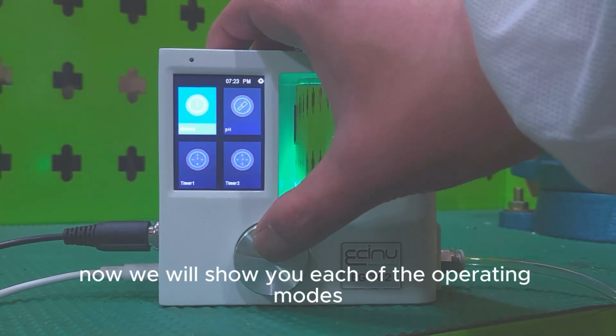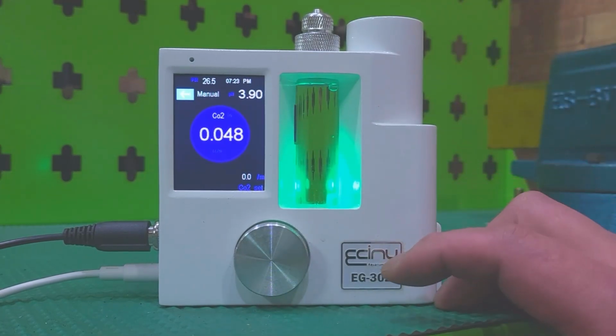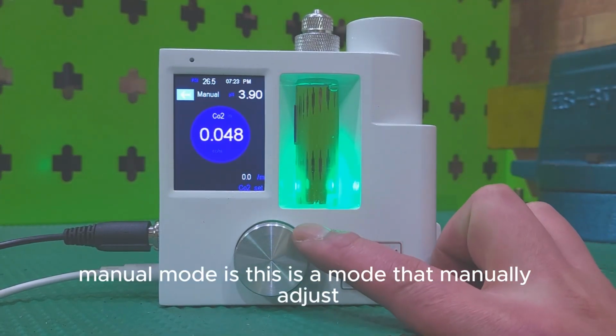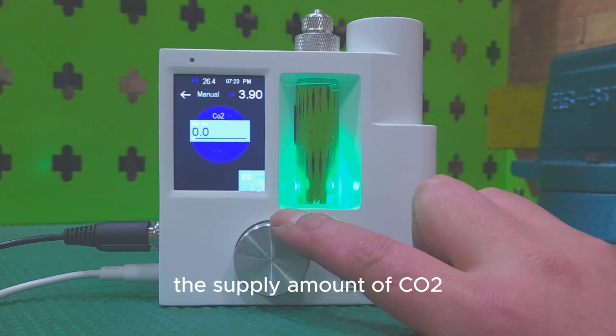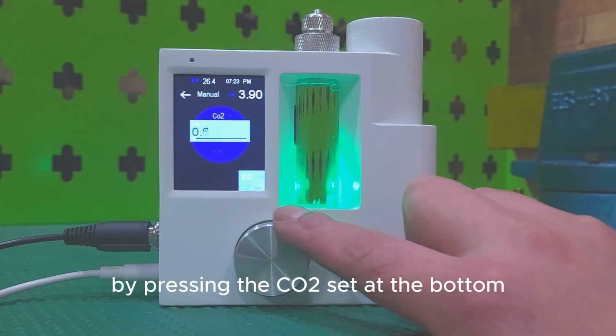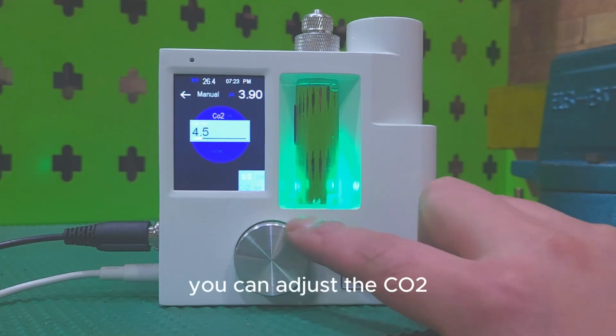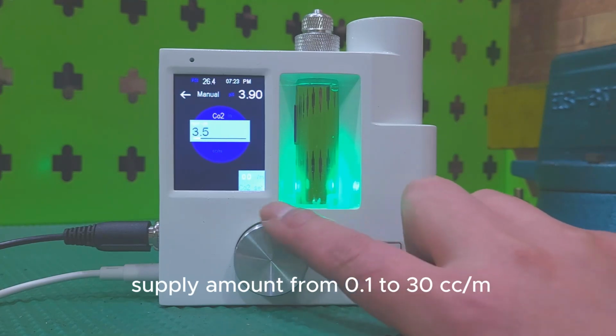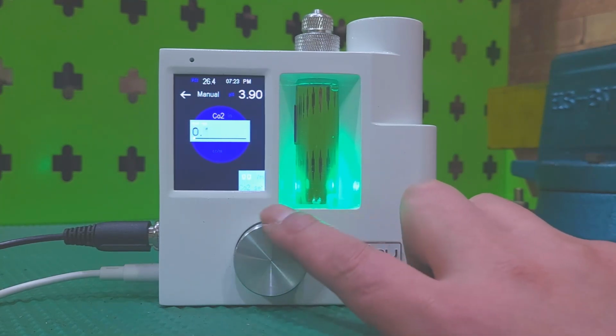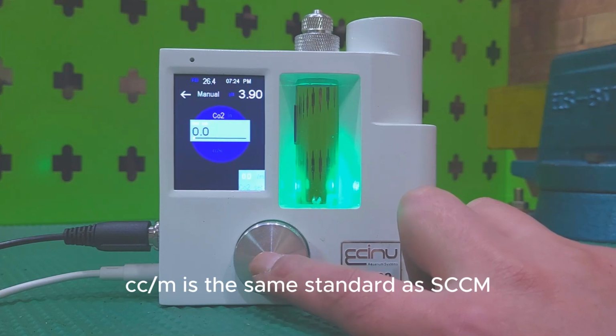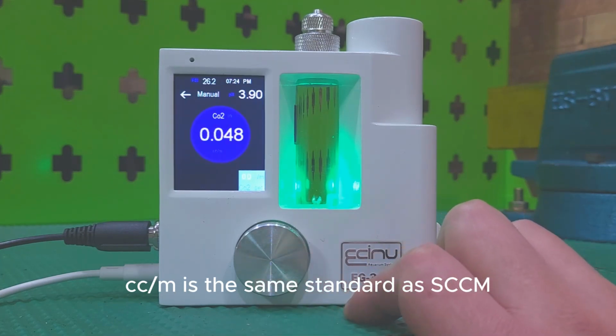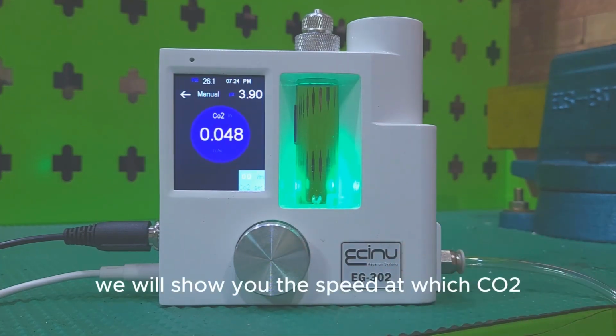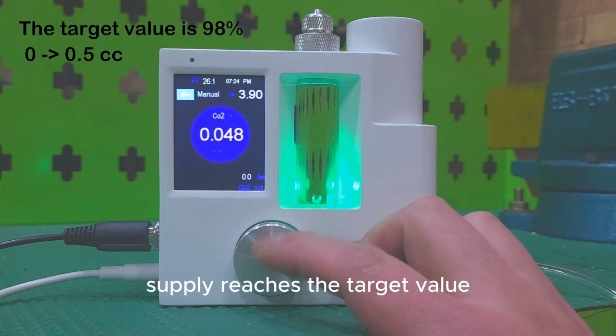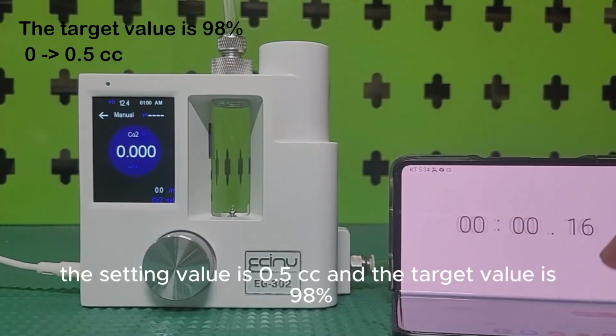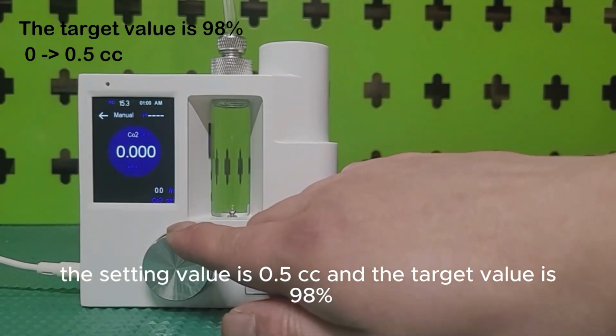Now we will show you each of the operating modes. Manual mode is a mode that manually adjusts the supply amount of CO2. By pressing the CO2 set at the bottom, you can adjust the CO2 supply amount from 0.1 to 30 ccm. ccm is the same standard as SCCM. We will show you the speed at which CO2 supply reaches the target value. The setting value is 0.5 cc and the target value is 98%.